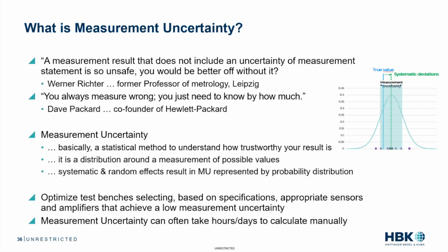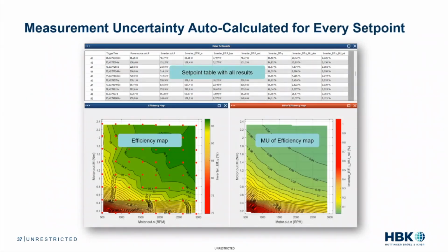Here is something really exciting that we have introduced just recently. The HBK solution offers the ability to automatically calculate the measurement uncertainty for every set point. This is really exciting. It's pretty cool, actually. You've got a set point table with all the results, and you can select whatever results you want to include in the table. It's up to you. But more importantly, you've got an efficiency map on the left, and on the right, you have a measurement uncertainty graph of the efficiency map. So now you can identify which parts are more trustworthy than others in your measurements.